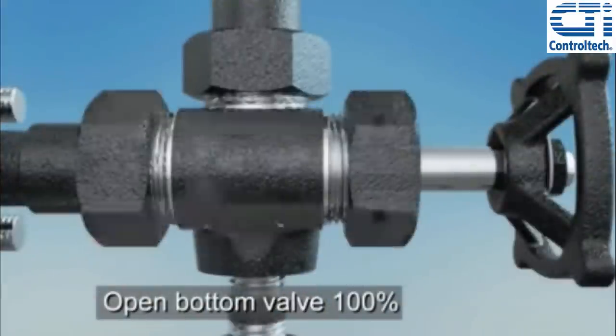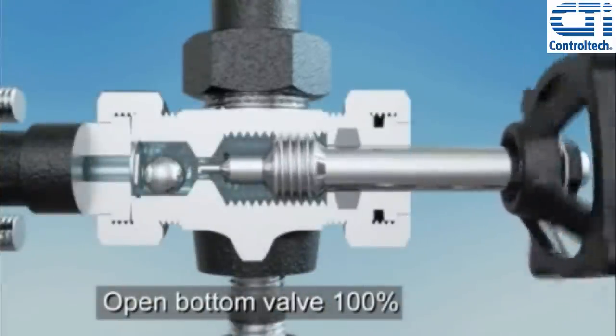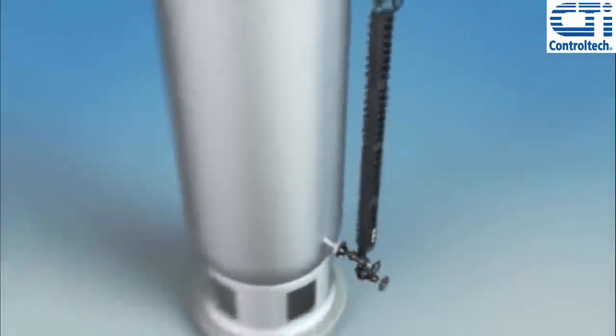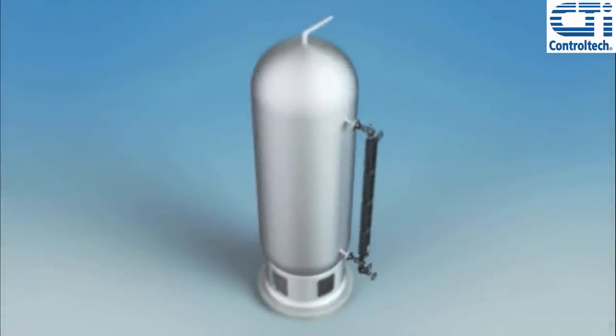Next, fully open the bottom valve. The tip of each stem has now been retracted into its seat cavity, allowing the ball checks to engage in the event of a catastrophic failure.